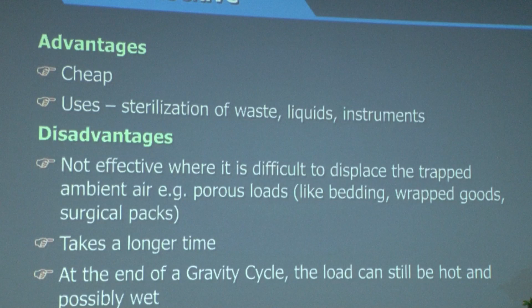The steam is then let, made to enter the inner jacket, wait for it to reach 121 degrees Celsius at 15 psi for 21 minutes, the sterile cycle, and then the drying cycle is altered. So you have to teach your paramedical staff of all these parameters of time, temperature, and pressure. These are the disadvantages and the advantages of a traditional vertical autoclave.